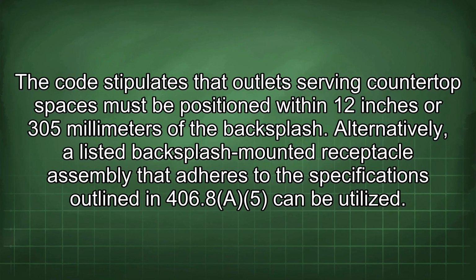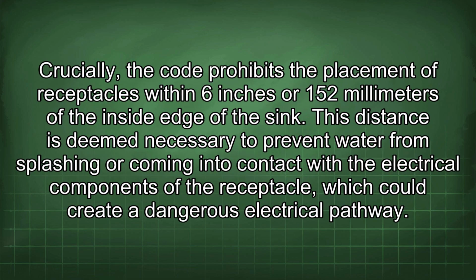The code stipulates that outlets serving countertop spaces must be positioned within 12 inches or 305 mm of the backsplash. Alternatively, a listed backsplash-mounted receptacle assembly that adheres to the specifications outlined in 406.8(A)(5) can be utilized. Crucially, the code prohibits the placement of receptacles within 6 inches or 152 mm of the inside edge of the sink. This distance is deemed necessary to prevent water from splashing or coming into contact with the electrical components of the receptacle, which could create a dangerous electrical pathway.